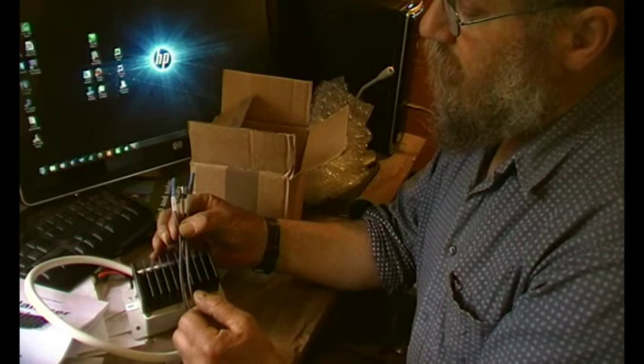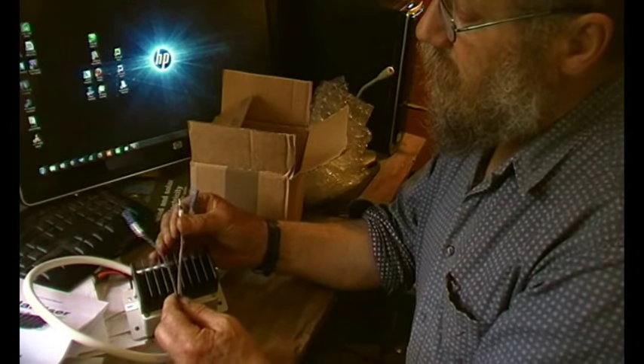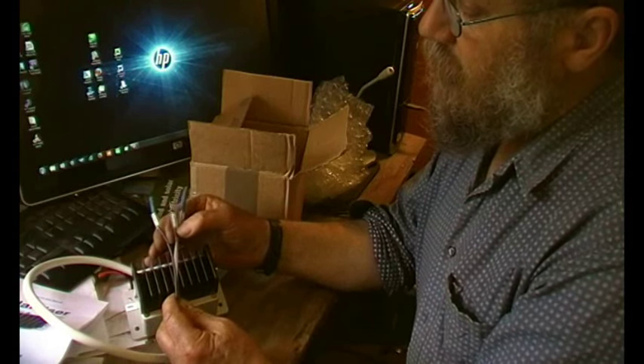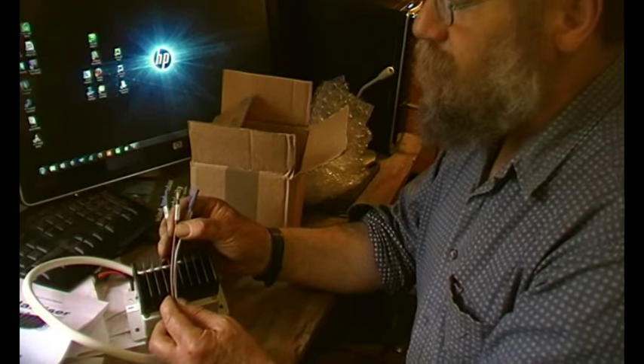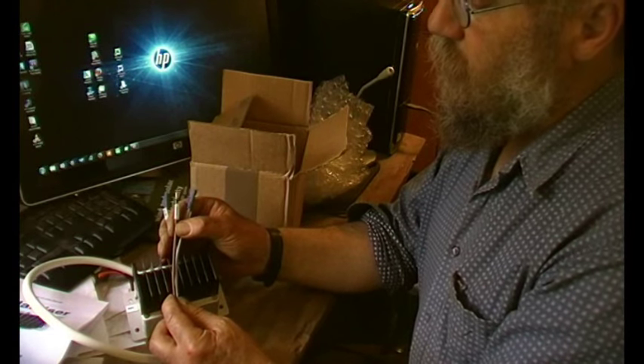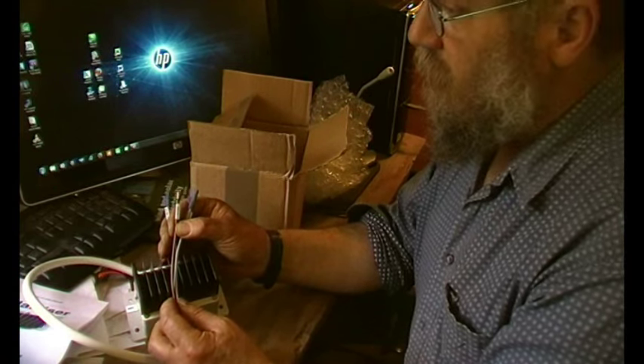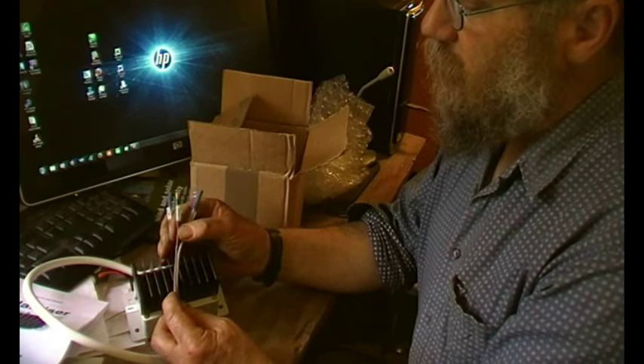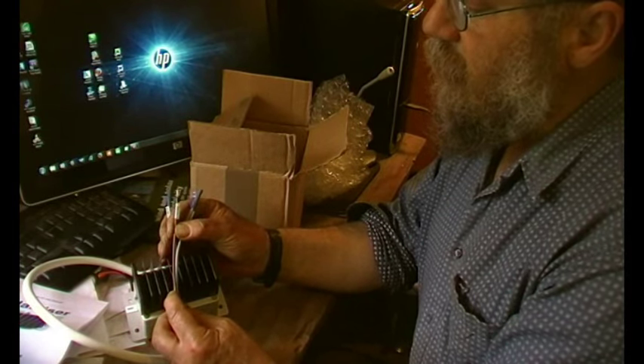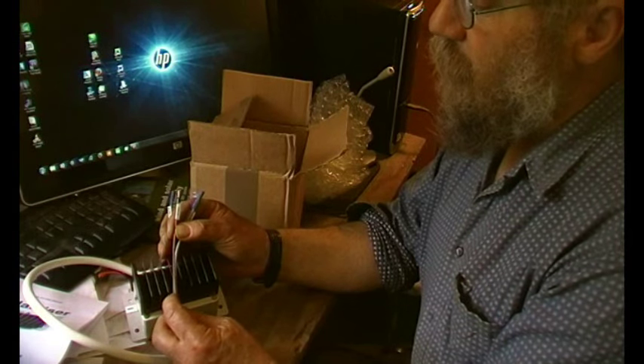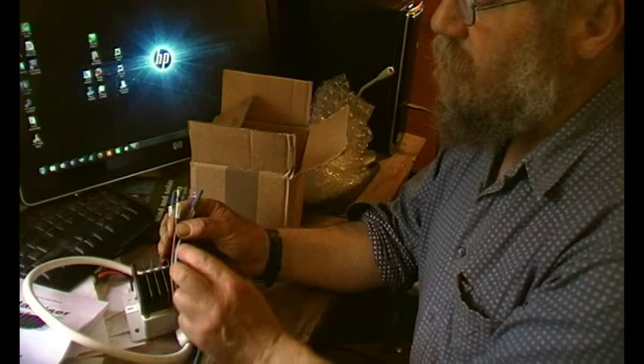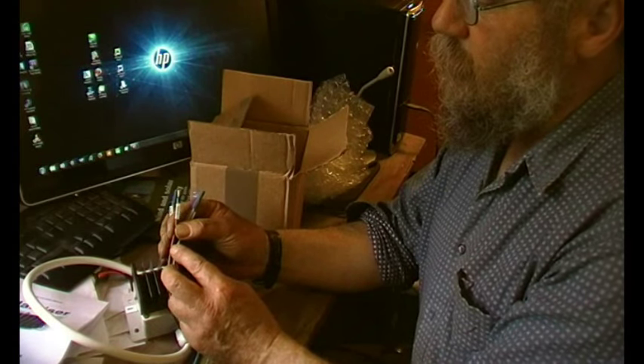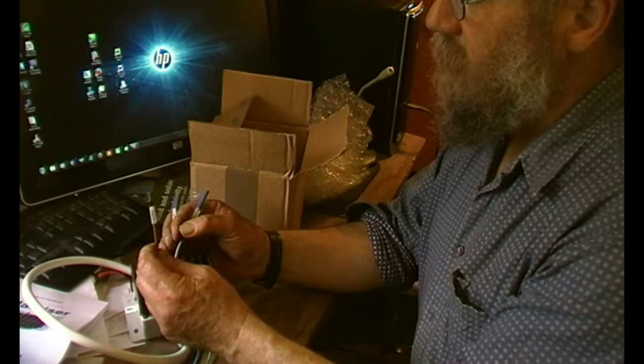OK, then what else have we got? They're all nicely labelled. Where your immersion heater is, there's obviously a fuse or an MCB version of a fuse. So basically, you take the wire out that goes to your immersion heater from that disconnect method by the fuse or the MCB and you poke that in there.